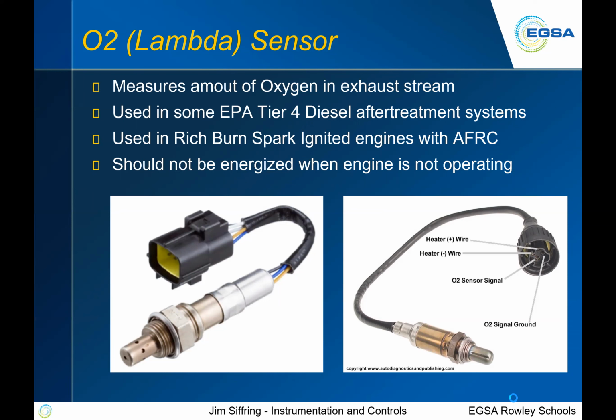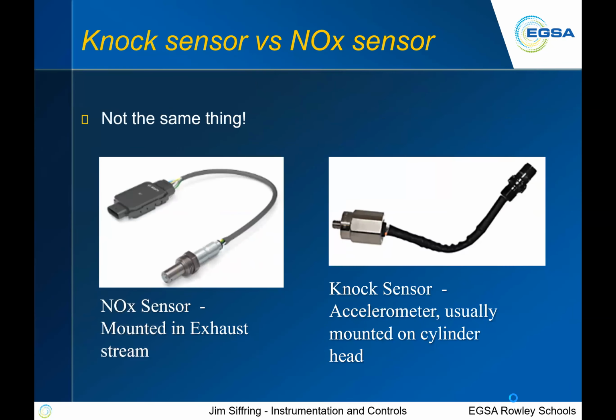Often that's the input to an air fuel ratio controller that gives it the feedback loop to tell the ratio controller what it needs to do, whether it needs to add fuel or reduce fuel. One thing to note, they shouldn't be energized when the engine is not operating. Typically, these elements are heated, but if they're heated and they don't have an exhaust stream going across them, they'll typically burn out. Now, that happens pretty much automatically on pretty much all engines these days, but just keep in mind.